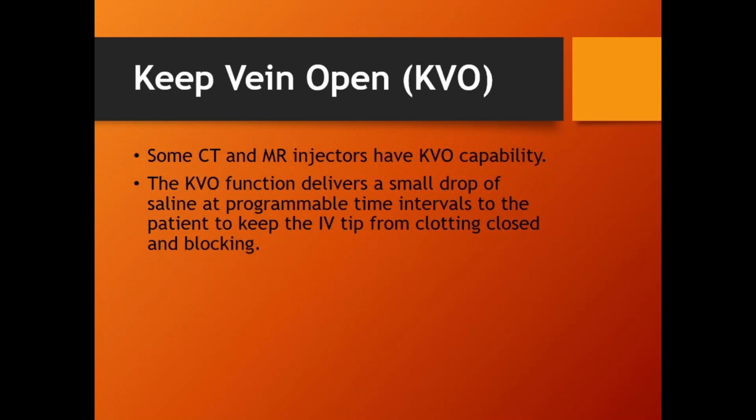Exactly. All right. Not every injector does this, but there is something called KVO, which means keep vein open. This is for CT and MRI injectors. Angio injectors don't do this. This is for CT and MRI because remember, CT and MRI use IV needles to perform the injections. Angio injectors use catheters.